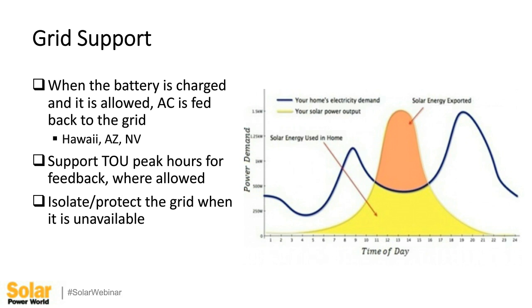You've got to be real careful with this. You need to check with your local utility providers. Some of them allow feeding back from batteries. Some of them restrict it as only being allowed to be charged from the PV system. You can't charge from the grid and then feed it back to the grid at a better time. You need to check with your local jurisdictions, your local utility companies, and find out what their restrictions are.